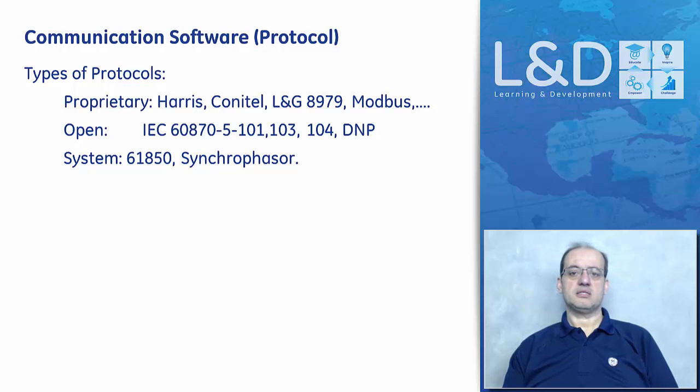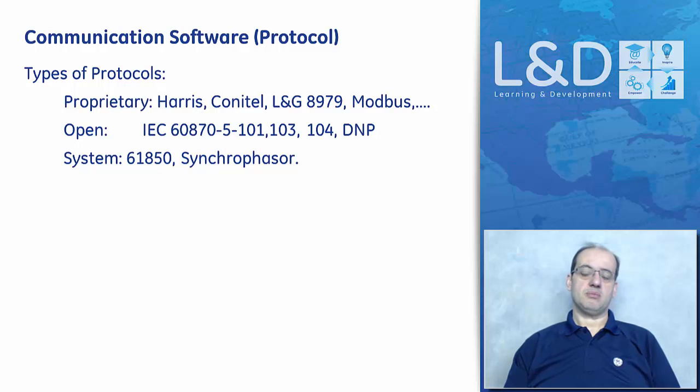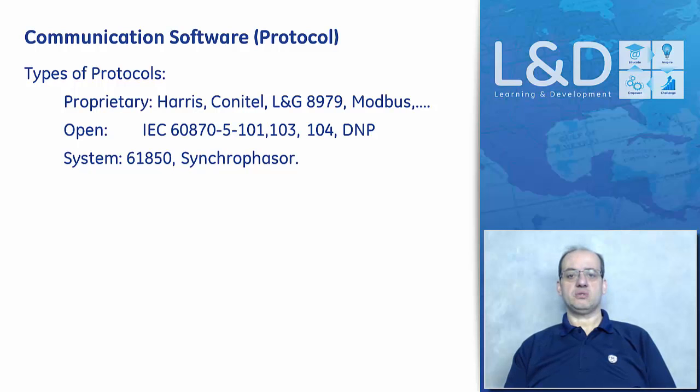In the 1990s, the idea came of taking these protocols a step ahead and instead of having a protocol, have a system. And the system is like the Utility Communication Architecture or the 61850. Both of them rely on a different kind of communication. So instead of relying on a poll and a reply, they would rely on publisher and subscriber. A publisher would send data constantly after the handshake, and the subscriber would receive this data and parse it for the required subset of information that he requires. This minimized and more efficiently used the network communication.